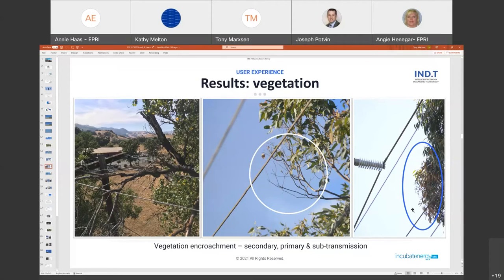It's a secondary bare wire service, and the dead branch across the three wires has obviously sat there for a long time and had time to dry out. But it was a green sapling, a bit off to the right, not in the photo, that was probably the thing we were picking up. Dead branches like that actually become quite good insulators after a while.